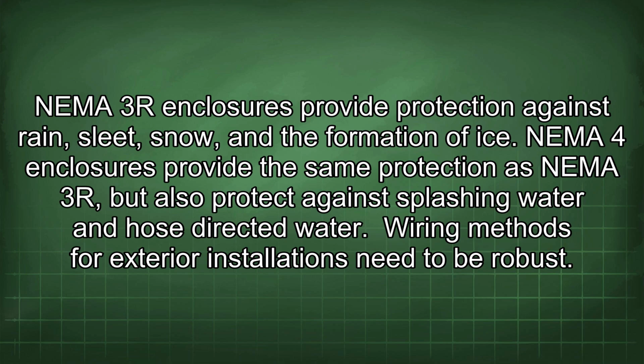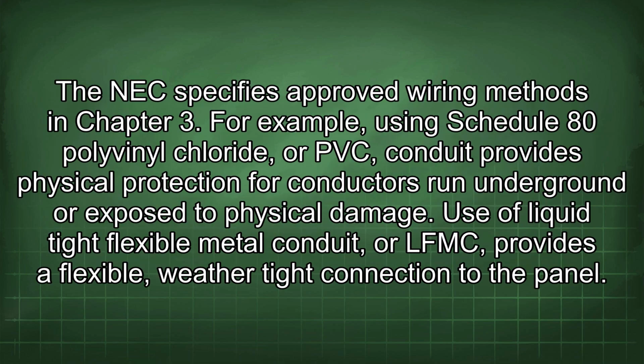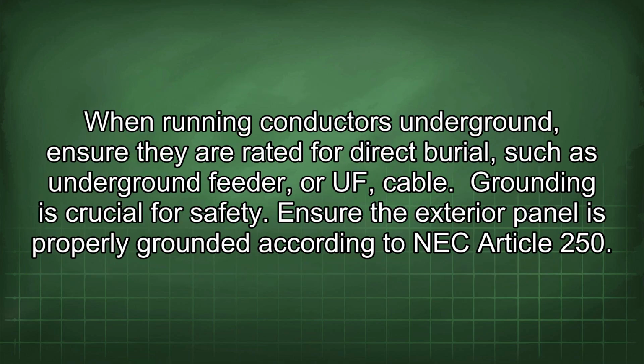Wiring methods for exterior installations need to be robust. The NEC specifies approved wiring methods in Chapter 3. For example, using Schedule 80 polyvinyl chloride, or PVC, conduit provides physical protection for conductors run underground or exposed to physical damage. Use of liquidtight flexible metal conduit, or LFMC, provides a flexible, weather-tight connection to the panel. When running conductors underground, ensure they are rated for direct burial, such as underground feeder or UF cable.